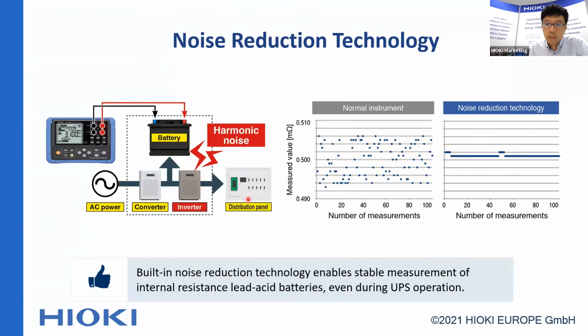During UPS operation, there is harmonic noise from the inverter. If the frequency of the inverter noise is close to the measurement frequency of the battery tester, stable measurement is not possible. To solve this problem, HIOKI developed a noise reduction technology. If you use this function, the device detects the noise frequency at the beginning of the measurement and starts measuring, giving you a very stable measurement result like this.